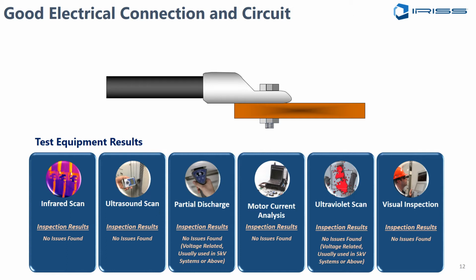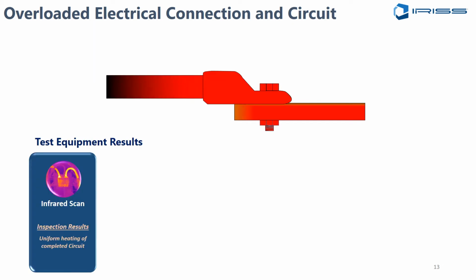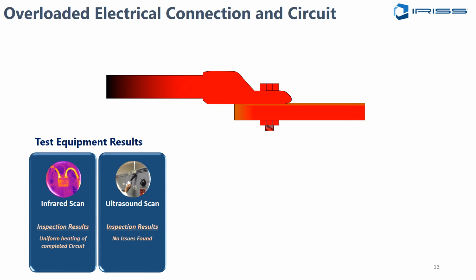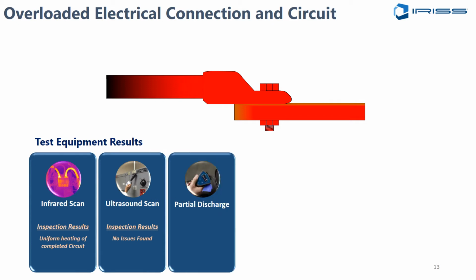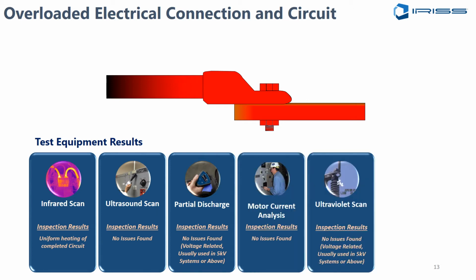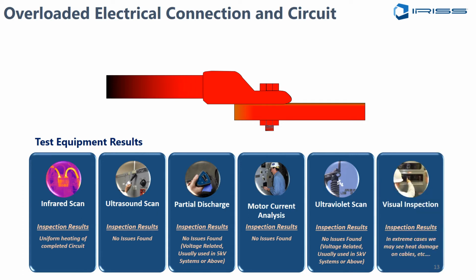Now, if you look at an overloaded electrical connection, by utilizing the same test equipment, the infrared scan is going to show me uniform heating of the circuit. Ultrasound possibly is not going to show me a lot at this stage. PD, again, if it's over 5 kV, we might see it, but for overloads, this isn't really a circuit failure, this is a system failure, so we're not going to see anything. Motor current analysis, possibly not, only from the load readings, obviously. Ultraviolet scan is not going to show me anything, and with the visual inspection, only in super extreme cases where the heat damage on the cables is severe will we see visual verification of that fault.